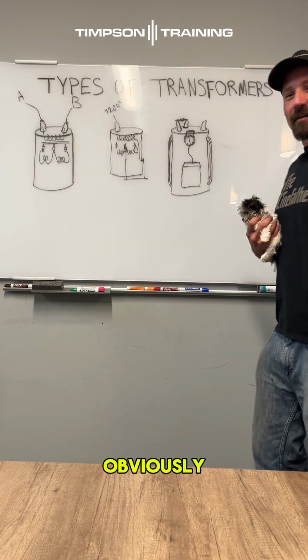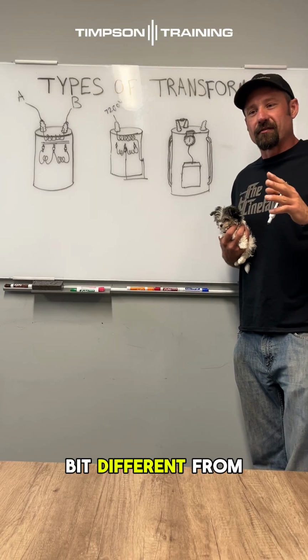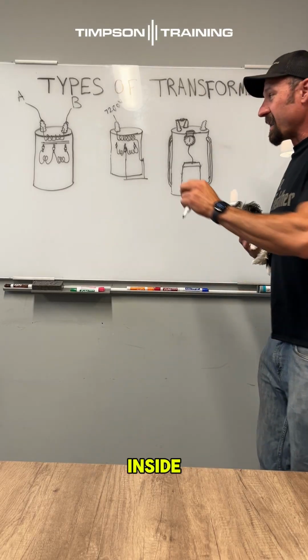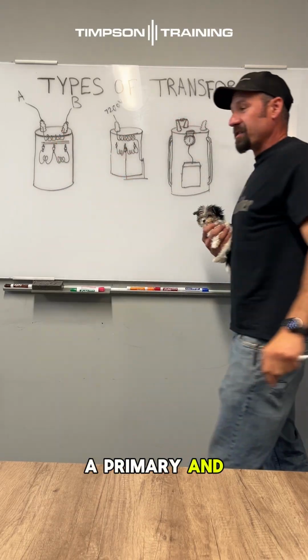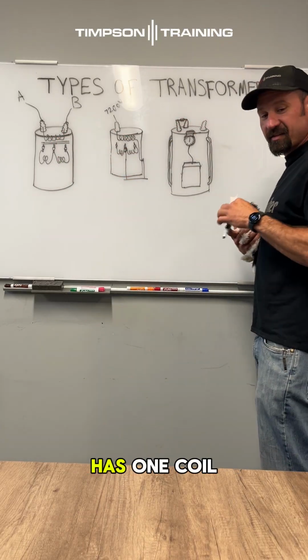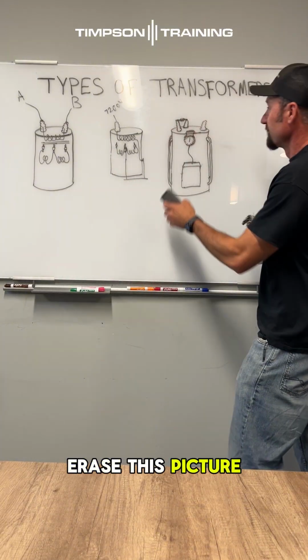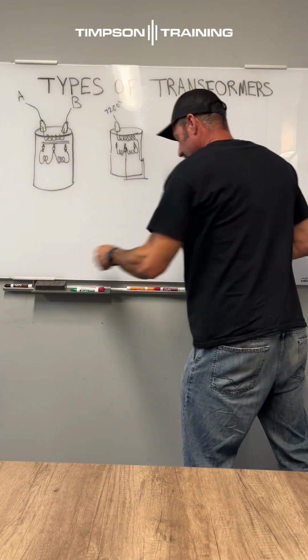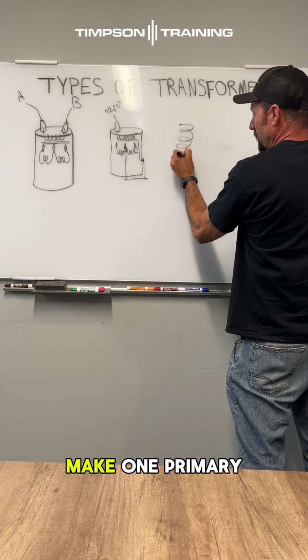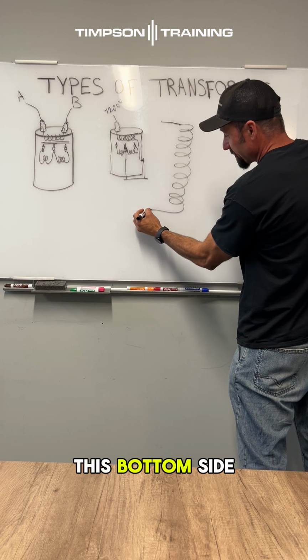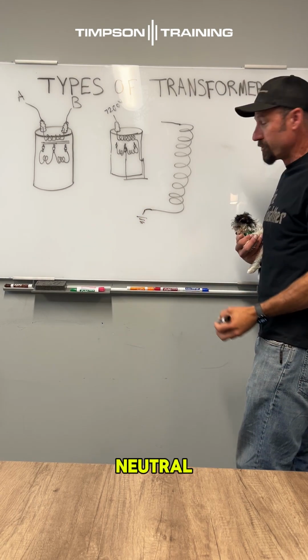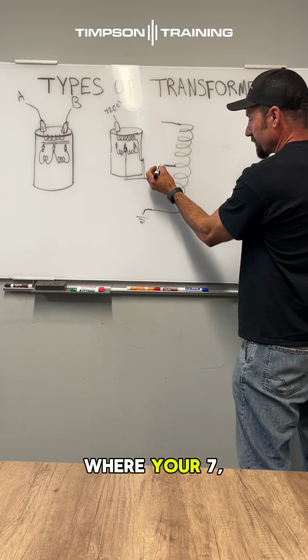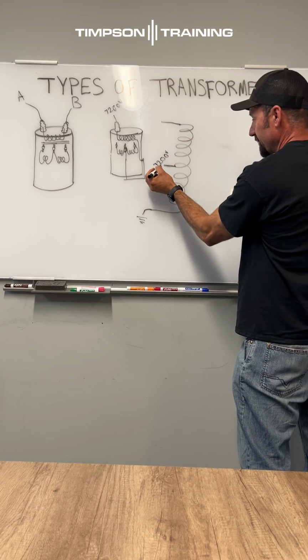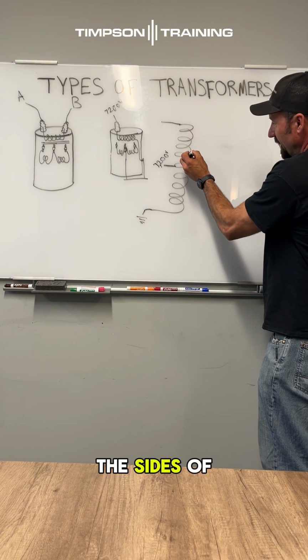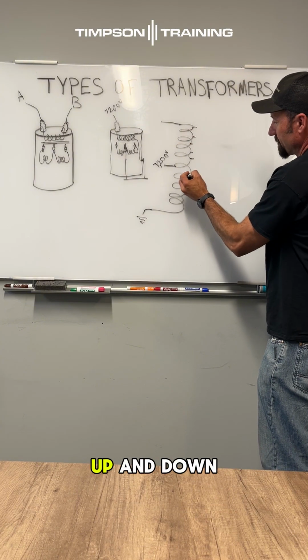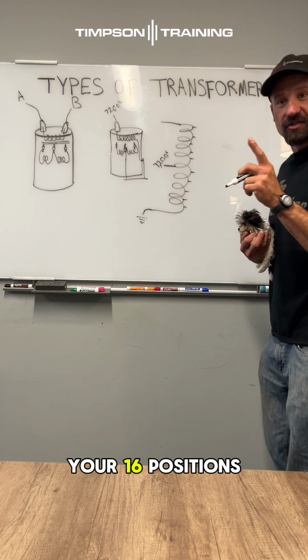So the regulators, obviously, this transformer is a little bit different from the other two. So if we're looking on the inside, unlike these where they have a primary and a secondary coil, a regulator only has one coil. So if I erase this picture and show you what's happening inside. So let's just make one primary coil, and we'll take this bottom side of the coil and ground it. That'll go to neutral. You'll have a mid tap here where your 7200 volts is going in. And then on the sides of these coils, you have little taps sticking off, up and down. Your 16 positions each way.